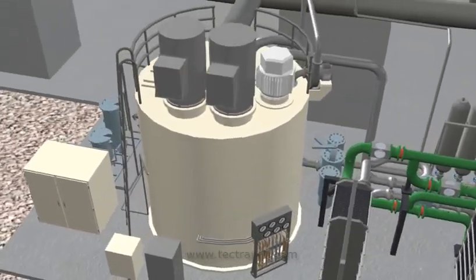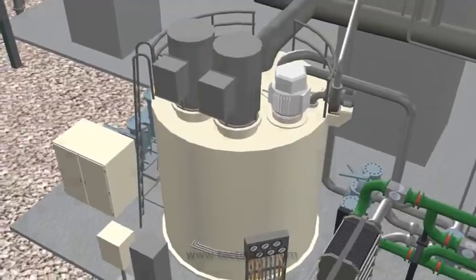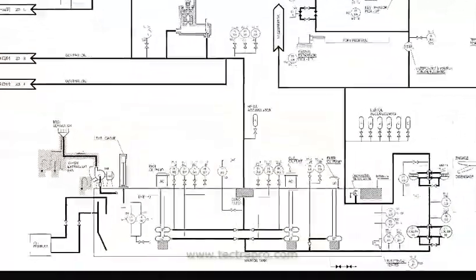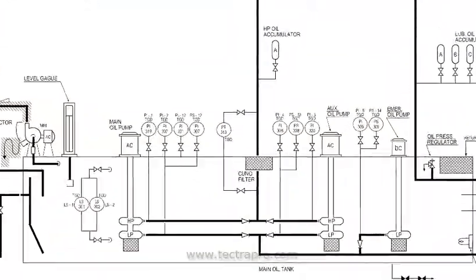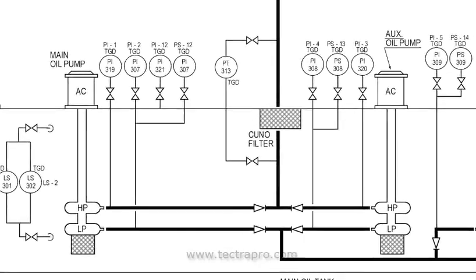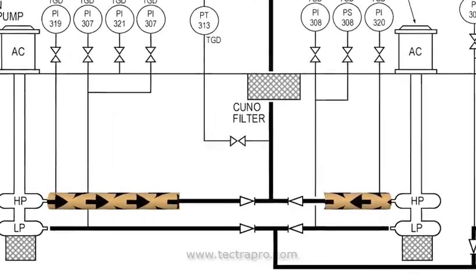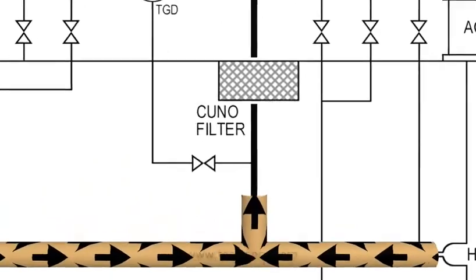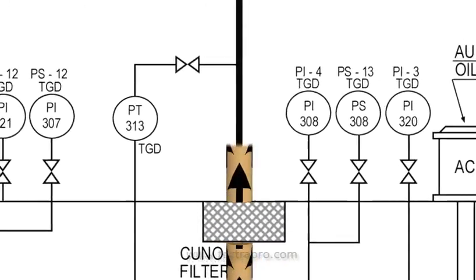Control oil is supplied from the same oil tank as the lubrication oil. High pressure control oil is supplied by the high pressure sections of the main and auxiliary lube oil pumps. The oil passes through a Cuno filter before leaving the oil tank area.